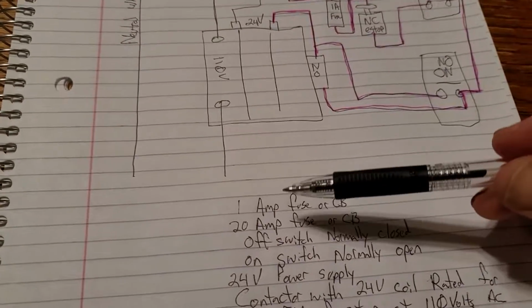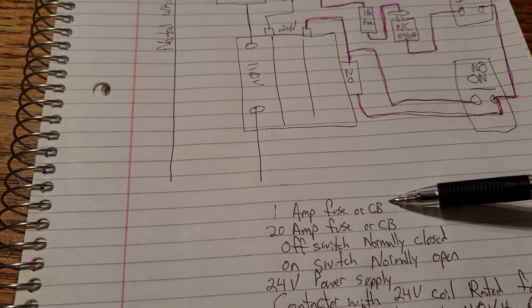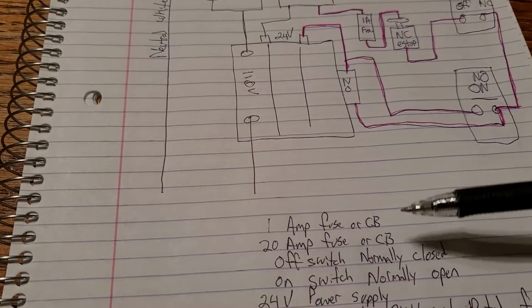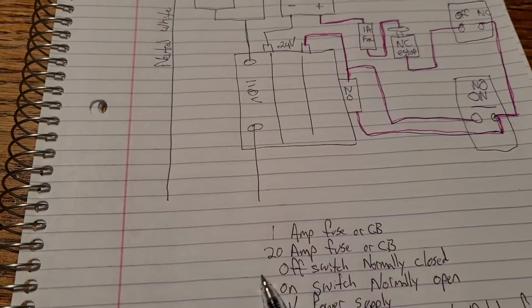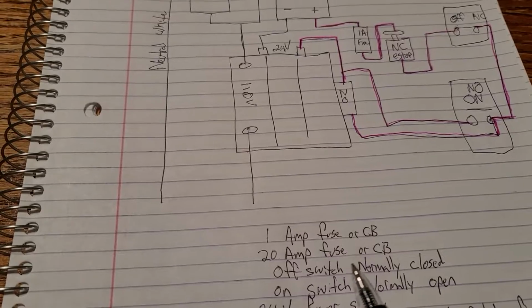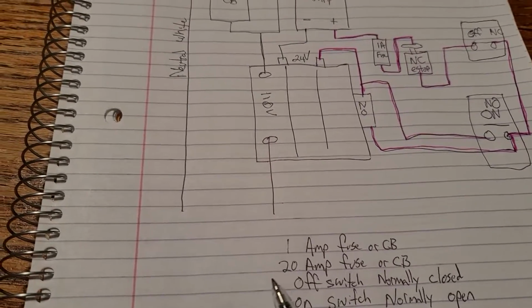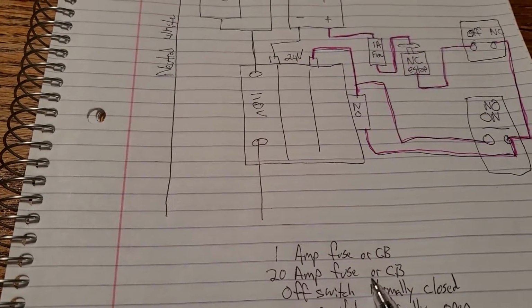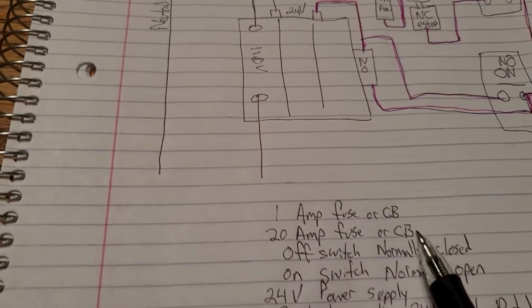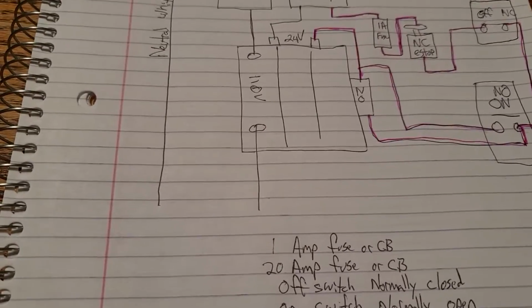So, you need a 1 amp fuse or circuit breaker, something real low amperage, and then something rated. So, if you're doing 110 volts at your house, that's 20 amps. So, get a 20 amp rated fuse or circuit breaker, DIN mounted for both those.